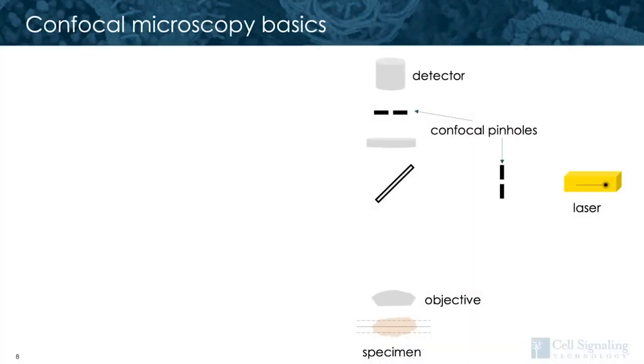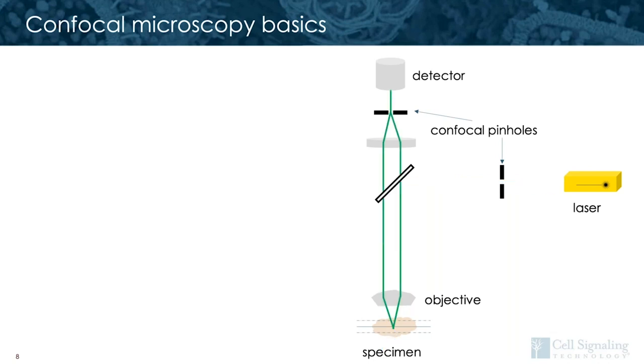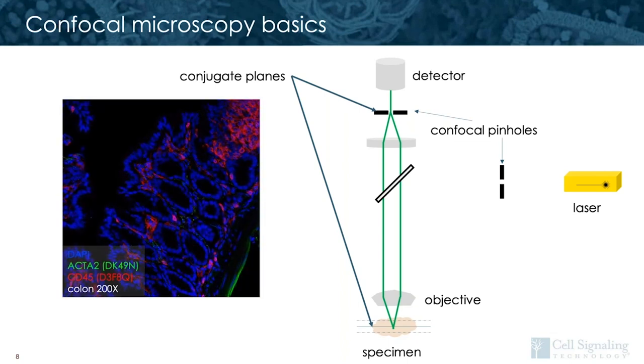Now that we've discussed the mechanics of an epifluorescent microscope, it's time to consider the confocal microscope. A laser scanning confocal microscope relies on lasers to excite the sample. This light is passed through a pinhole so that discrete points of light are directed across the sample with scanning mirrors. Emitted light from the sample is then directed toward another pinhole, and this allows you to image in conjugate planes. This is important for eliminating out-of-focus light from reaching the detector, and this is why confocal microscopes are able to take thin optical sections, where the thickness is determined by the size of the pinhole.